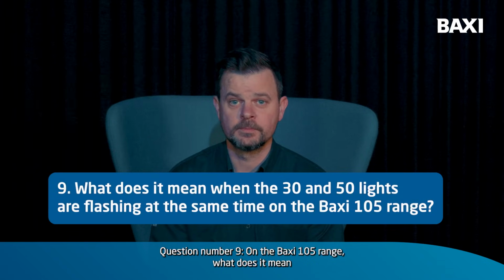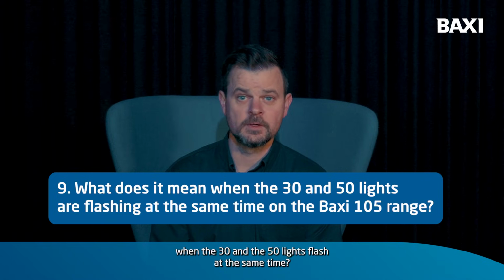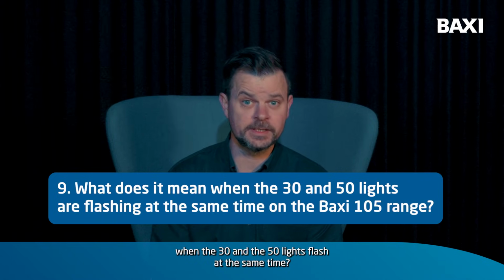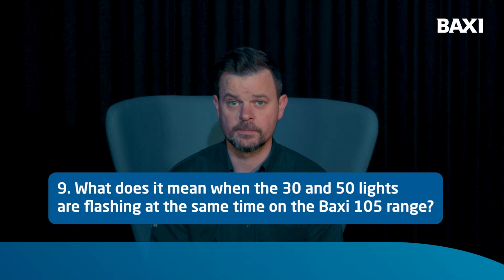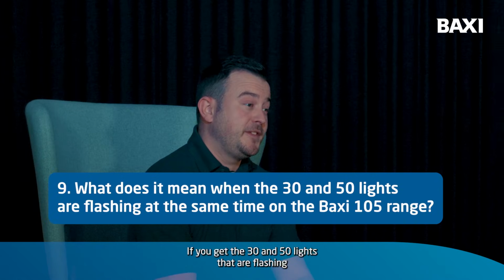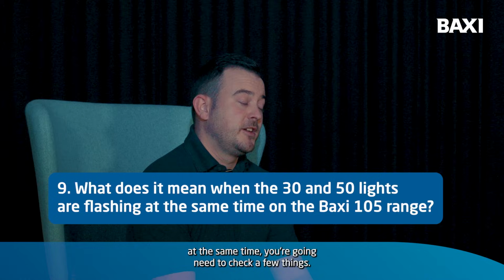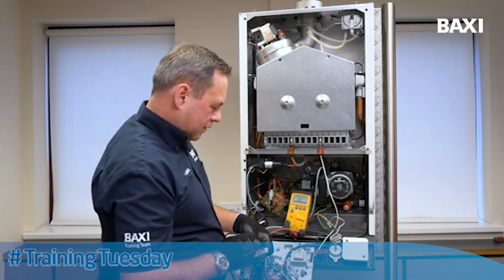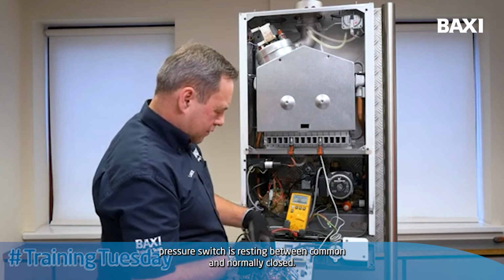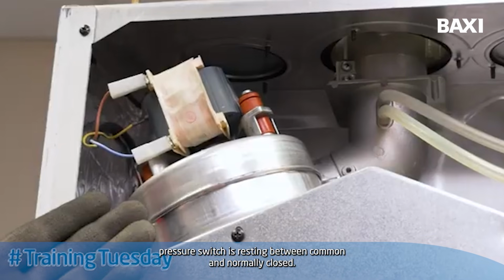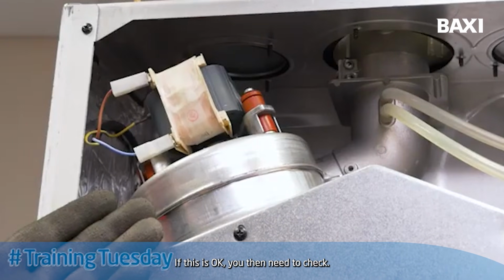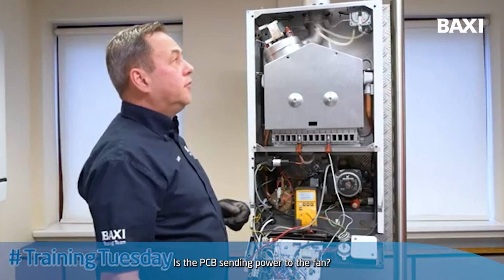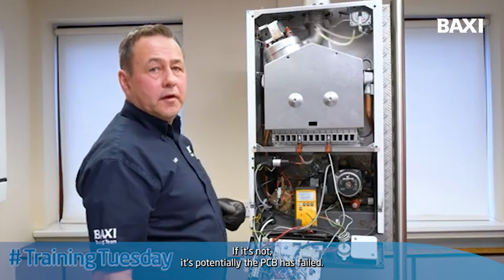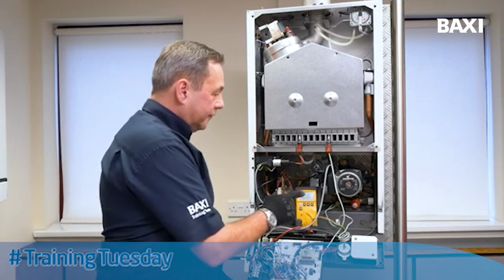Question number 9. On the Baxi 105 range, what does it mean when the 30 and the 50 lights flash at the same time? If you get the 30 and 50 lights flashing at the same time, you're going to need to check a few things. You need to check the air pressure switch is resting between common and normally closed. If this is okay, you then need to check is the PCB sending power to the fan. If it's not, it's potentially the PCB has failed.